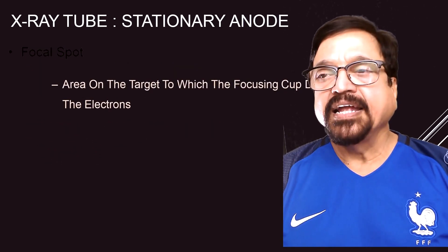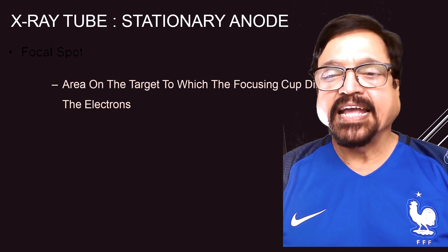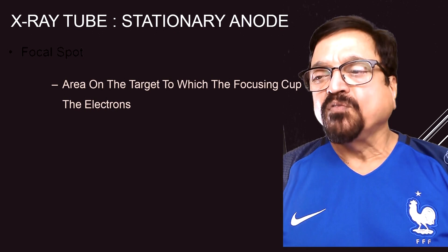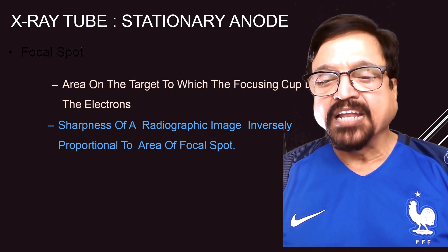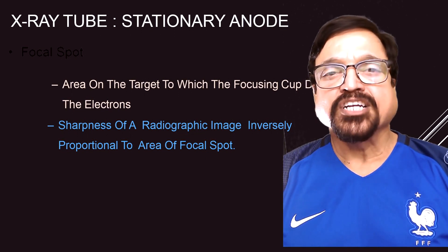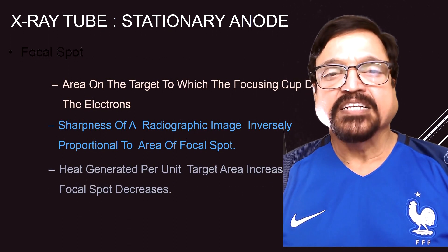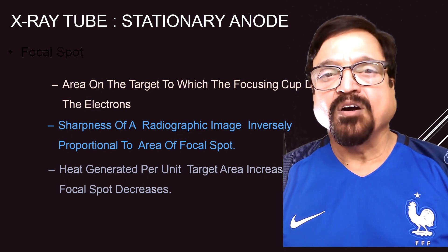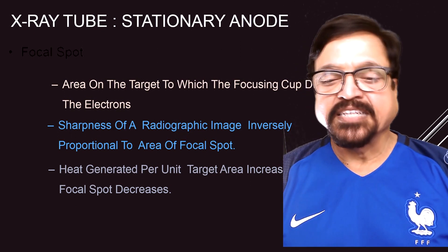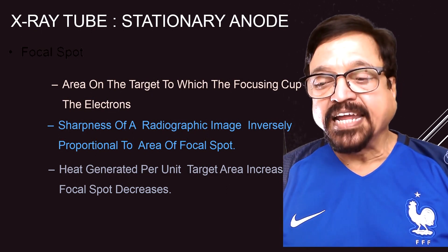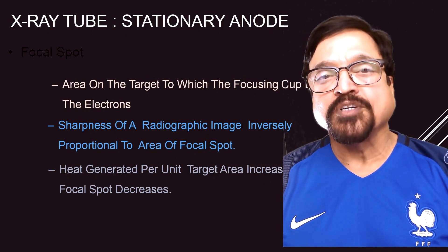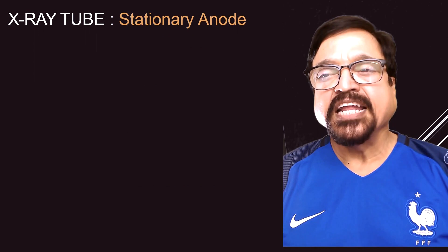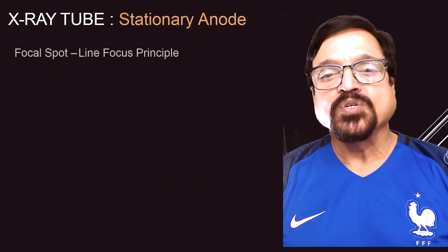Now let us come to certain technical aspects. What is a focal spot? It is the area on the target to which the focusing cup directs the electrons. The sharpness of a radiographic image is inversely proportional to the area of the focal spot. If you want a sharp image, the focal spot has to be small. If it is a large focal spot, the sharpness will not be there. When heat is generated, the size of the target area increases, which reduces the sharpness of the image. This is a limitation of the stationary anode tube, which can only be used in a few places.